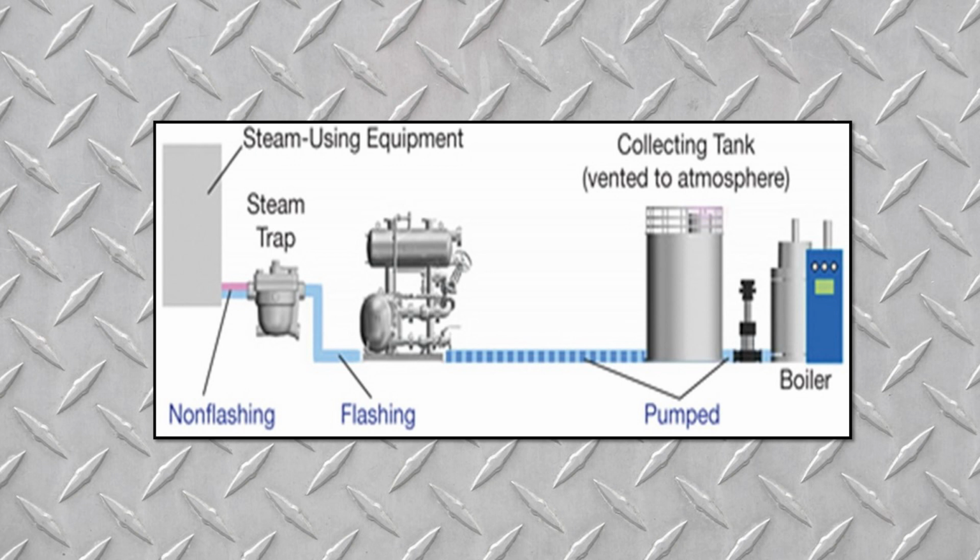Now, since plants can be noisy, often an ultrasonic sensing device can be used. You can point a wand or the sensor itself near the trap, and it can give you a great readout. Okay, so the condensate from these traps is generally collected and returned to a tank before being pressurized and put back into the boiler. Now, we want the stuff to be liquid in this condensate return system. However, if you have steam traps which have failed in an open position, they're now pushing steam into that condensate return system. And sadly, this is not rare and is not a good sign.